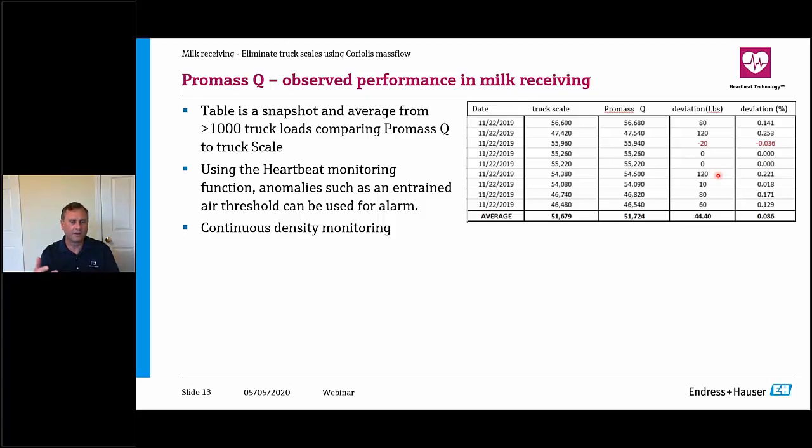And that's where we found these gasket issues, where the operators hadn't really hooked it up the right way. We were seeing others. So we could use this information to do continuous improvements and say, okay, how do we eliminate or minimize these kinds of manual errors, which otherwise would cause errors. Okay, so overall the accuracy is excellent, and we can use the diagnostics to continuously improve on it as well.